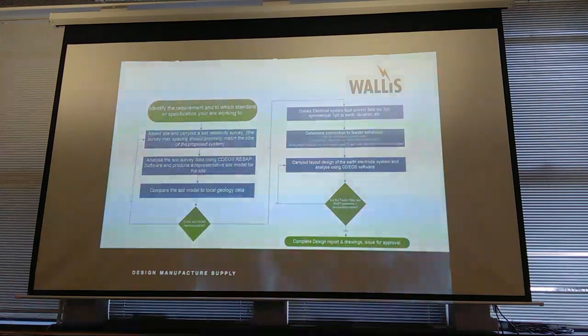So we then build all that up into the CDEGS model. We actually draw all the conductors onto the software itself. We put the soil model in. We tell it what fault level it's going to be at that specific site, and it analyses. It analyses the site, then it analyses the earth electrode system, and it tells us what the touch, step, transfer touch, step, and rise of earth potential values are going to be. We then, as engineers, need to be able to recognise whether they are within permissible limits or outside permissible limits. And those permissible limits are going to be down to ground coverings, clearance times, etc. But again, I'll touch on that more in the floor.